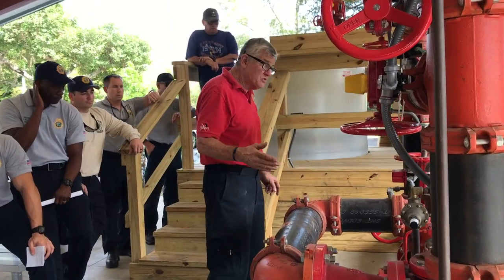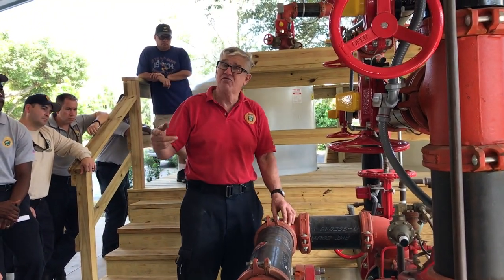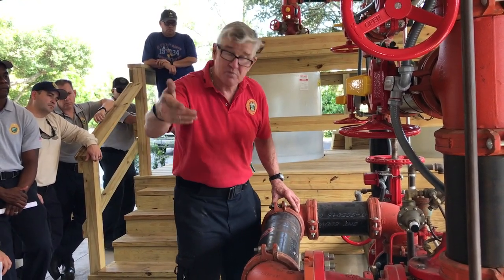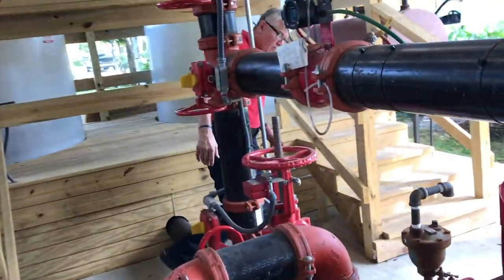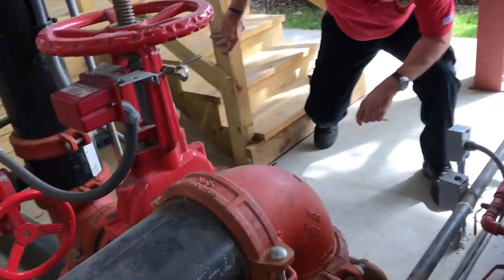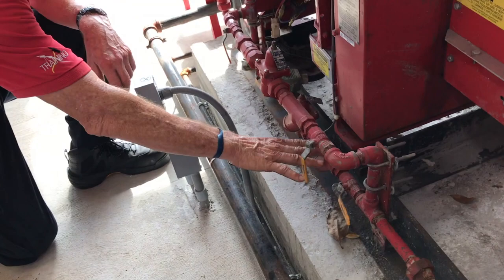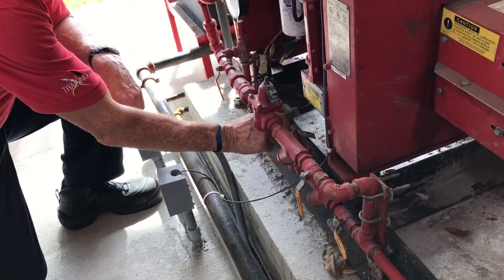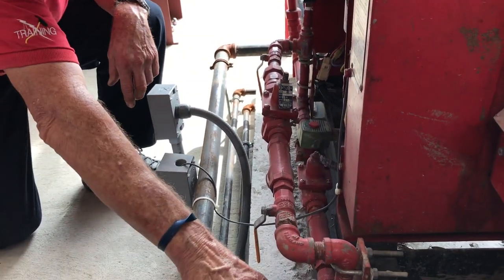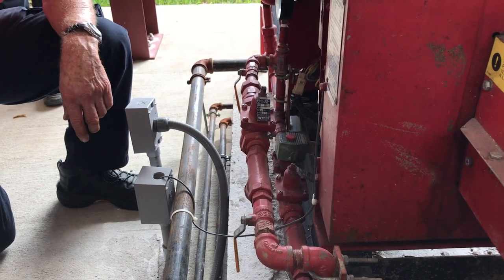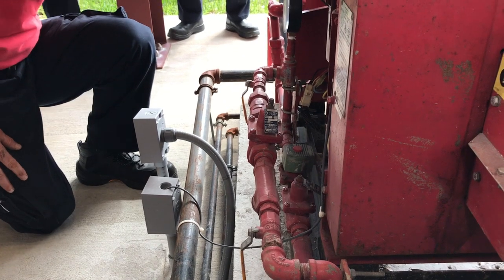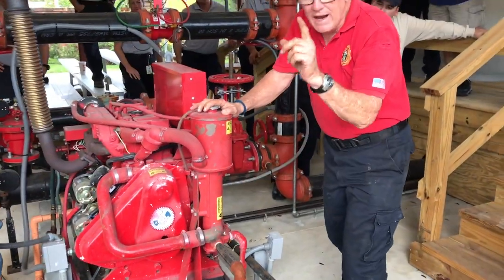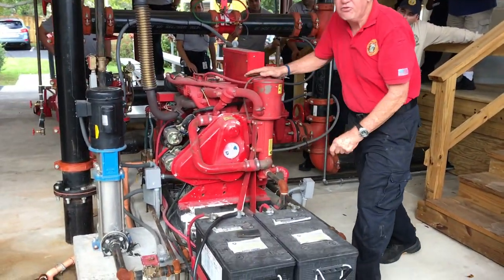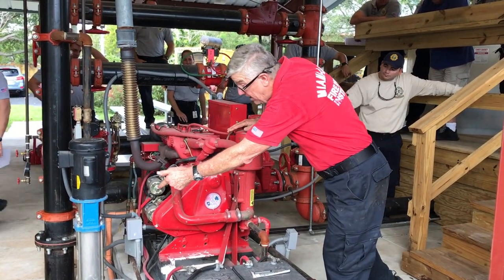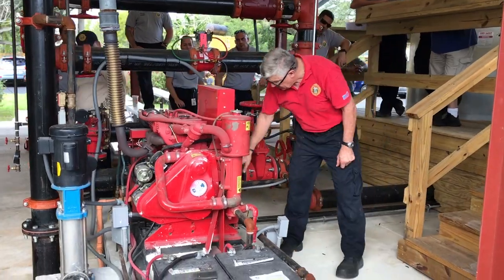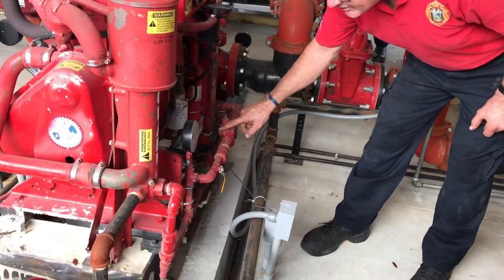Now, electric pumps have a relief valve. When the pump is not flowing or flowing very little, the relief valve will kick open to keep the pump cool. Over here, we have two cooling lines. This is the standard regular cooling line. Whenever you see this, this is an electrically operated valve. Water flows through here from the pump, so there's always water flowing through the pump, up into a heat exchanger, and then by design, by code, discharges on the floor. When you check the fire pump, go into the fire pump room, you want to see that water discharging. If you don't, there is an emergency line right above it that you can turn on to keep the pump cool.